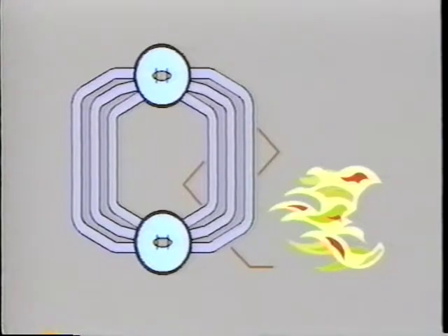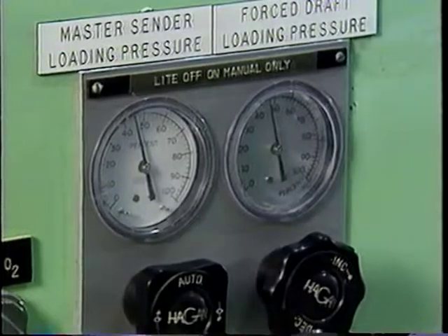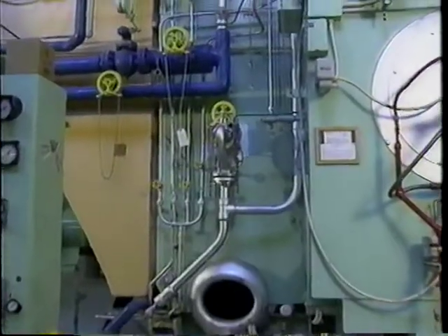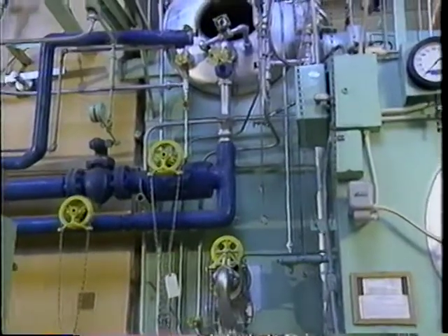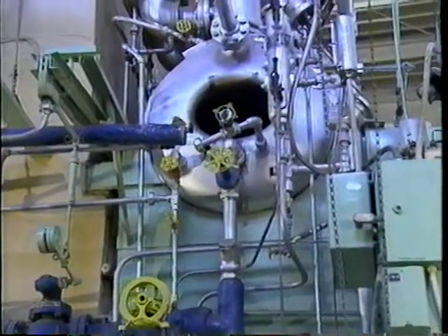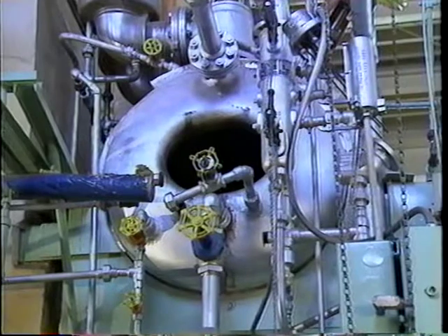Industrial water tube boilers are noted for their fast steaming capability, as there is less water to heat than a fire tube boiler. The low water content allows fast response to changing load demands. They are used for high-temperature hot water and high-pressure steam process applications. They are rated in pounds of steam per hour at operating conditions and range from 10,000 to 134,000 pounds per hour.